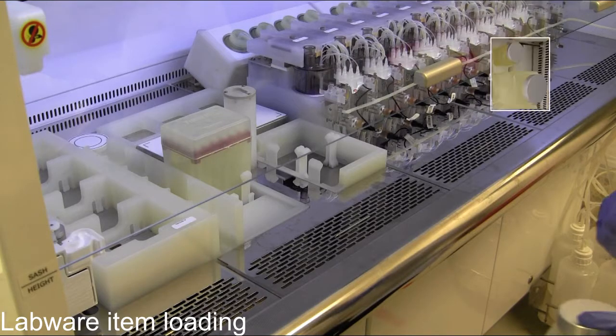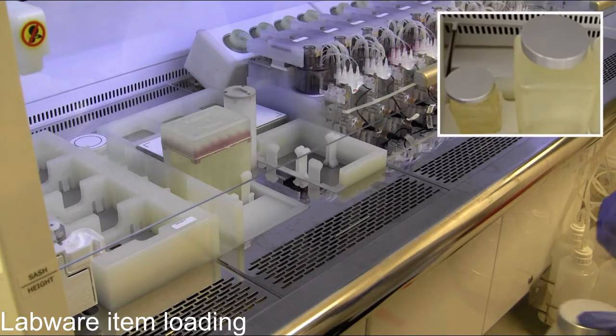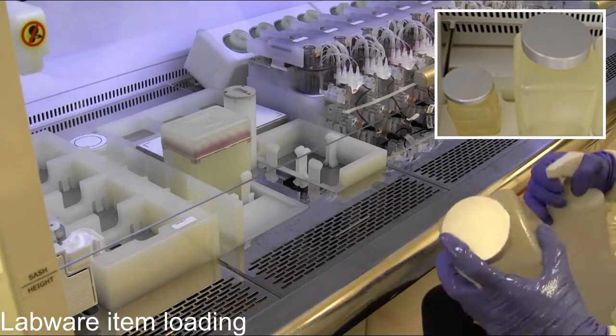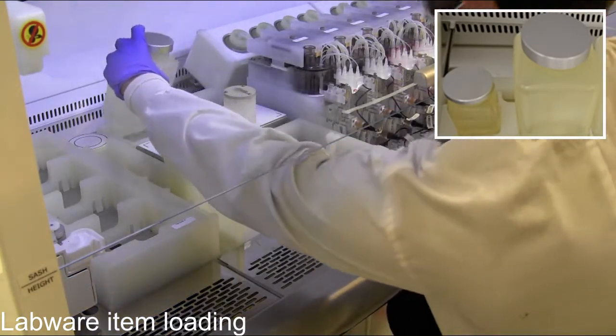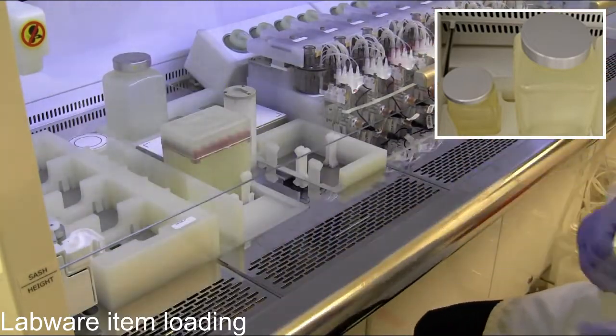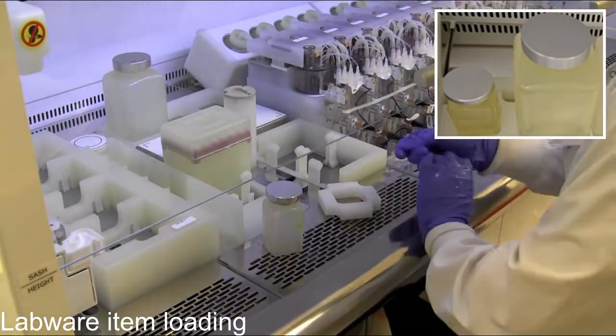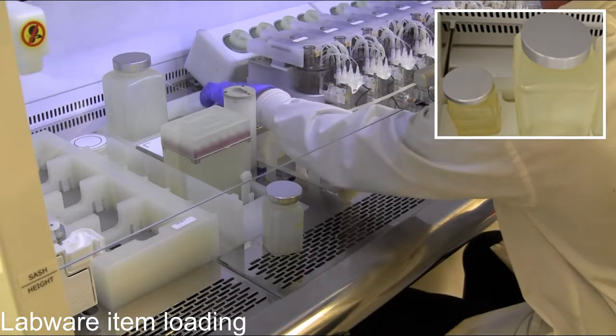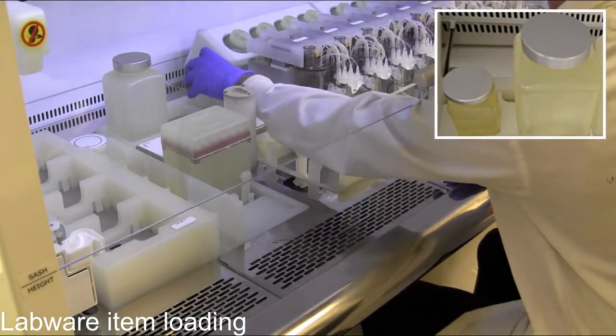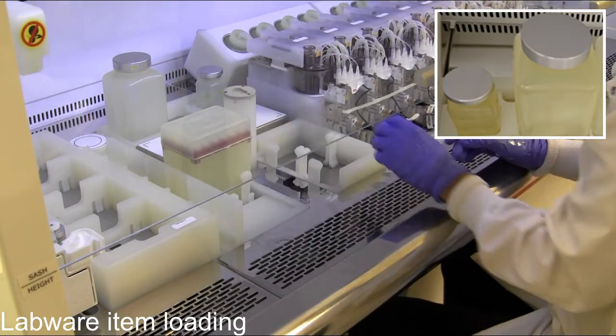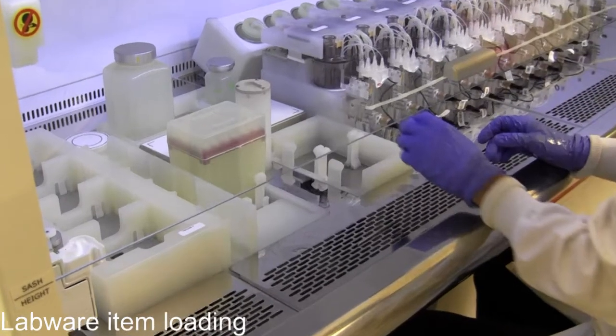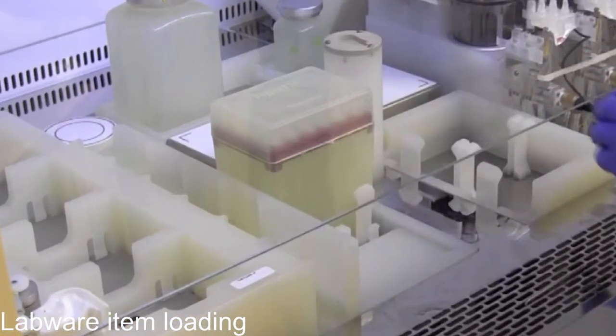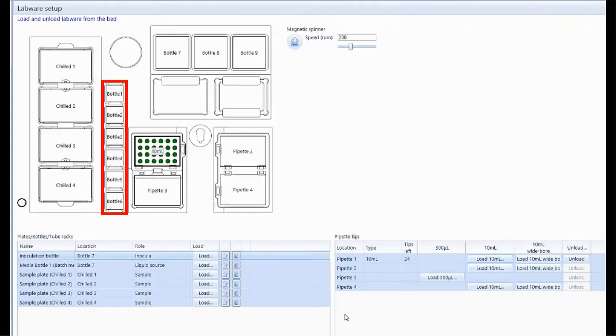Liquid containers come in 2 different sizes, 175 milliliters and 1 liter. The 1 liter bottle fits into any of the 3 stirred bottle positions in the back of the workstation. Use an adapter for the 175 ml bottle to ensure the bottle is aligned with the center of the stirred position, or use any of the 6 unstirred positions on the left. Ensure the reagent bottles are assigned to the correct position on the workstation in the software.